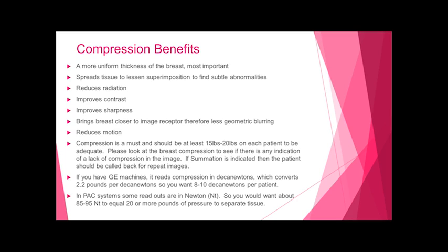Now there is a quality control test that you do on the equipment. It tests the equipment to make sure the minimum is 25 pounds of pressure and the maximum is 45 pounds of pressure. That's just testing the equipment. That's not saying that's the minimum or maximum you have on the patient. There's no law on compression limits.